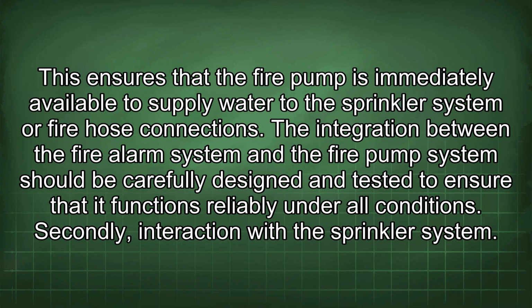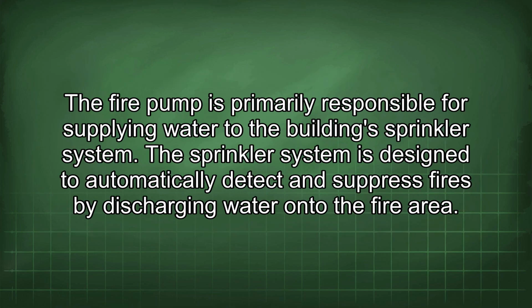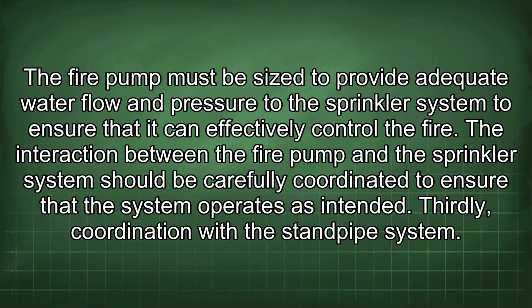Secondly, interaction with the sprinkler system. The fire pump is primarily responsible for supplying water to the building's sprinkler system. The sprinkler system is designed to automatically detect and suppress fires by discharging water onto the fire area. The fire pump must be sized to provide adequate water flow and pressure to the sprinkler system to ensure that it can effectively control the fire. The interaction between the fire pump and the sprinkler system should be carefully coordinated to ensure that the system operates as intended. Thirdly, coordination with the standpipe system.